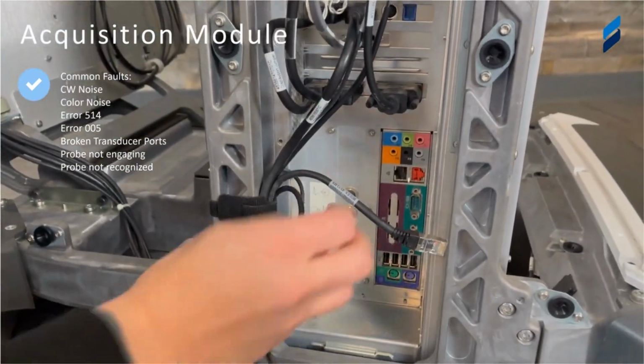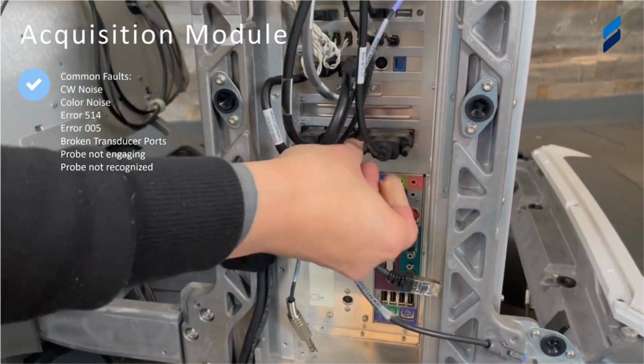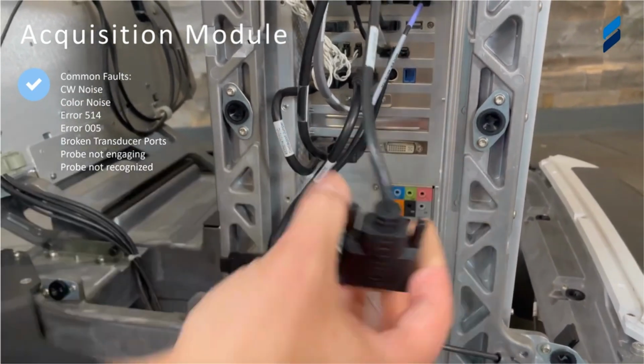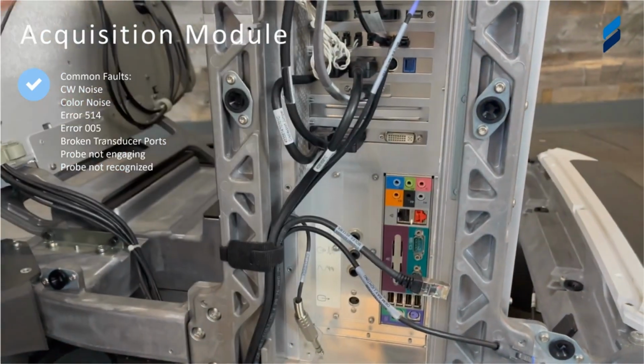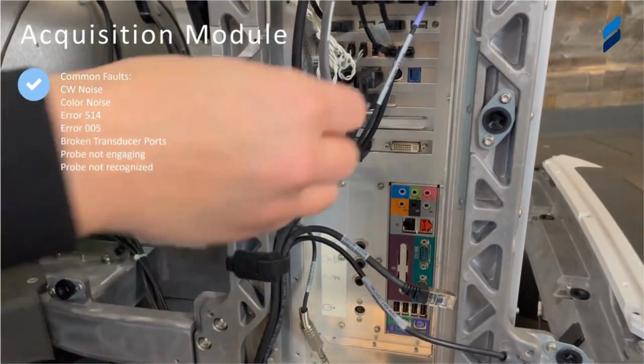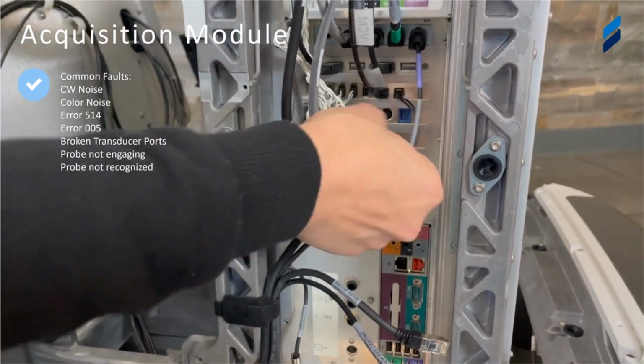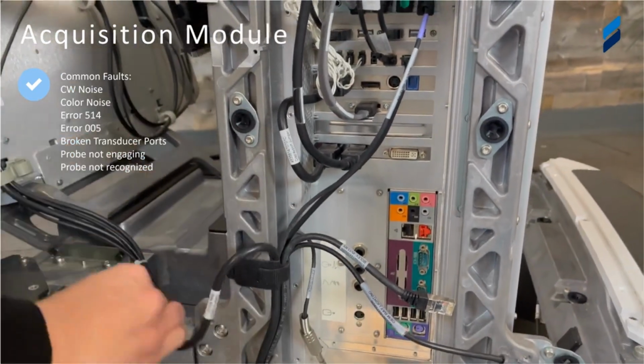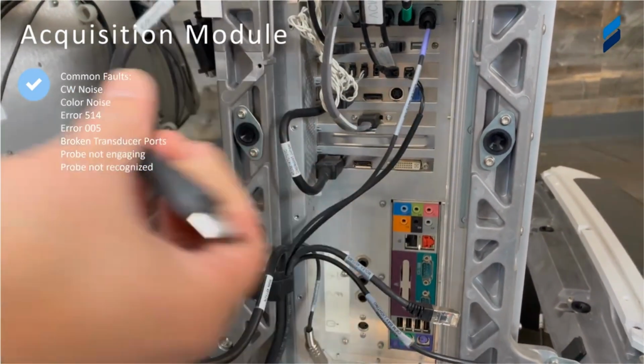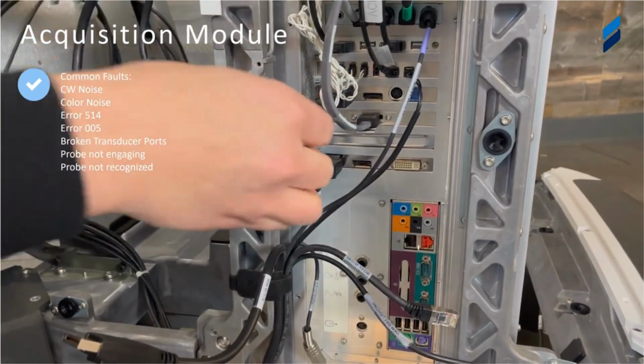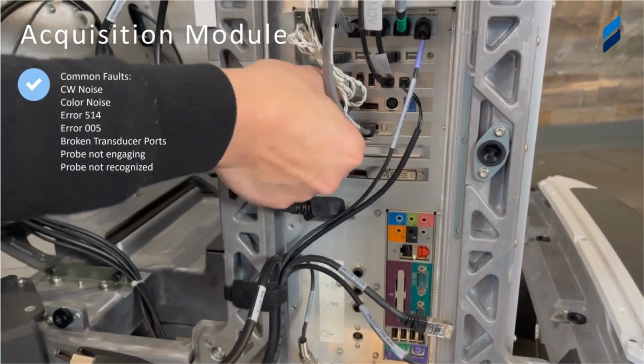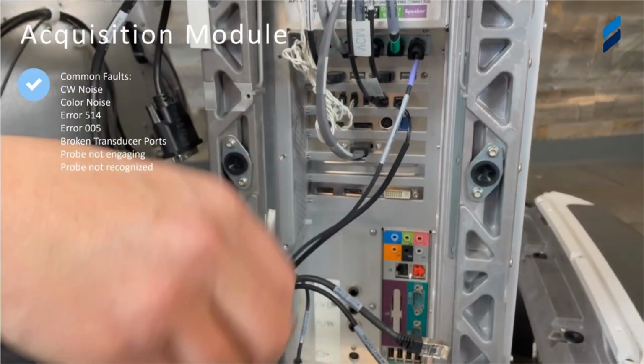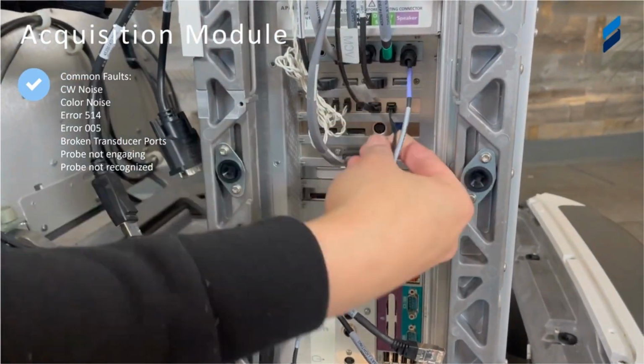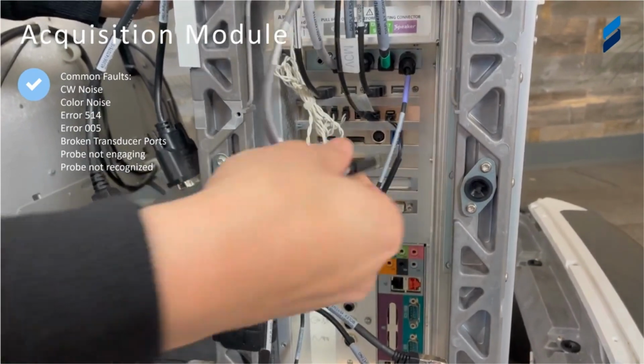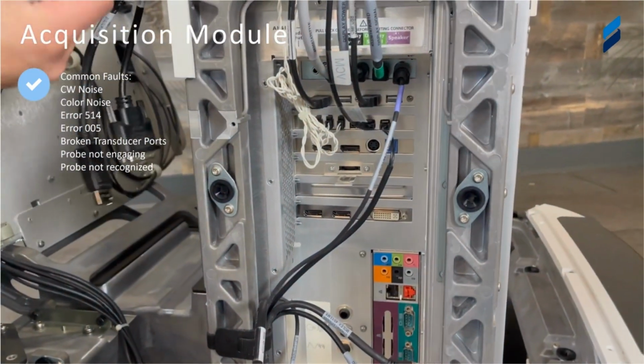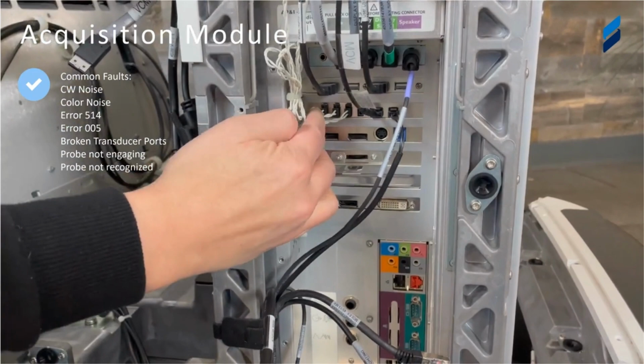Your acquisition module is that front piece that is attached to the e-box, but just for being thorough in this training, we're going to go ahead and remove all the connectors. Take pictures of your connectors and cables and where they go before you start removing them, so you know exactly where they go back. Referencing an external source of where your cables go is absolutely possible. We find that actually ends up taking more time than just pulling out your cell phone and taking a couple of pics on where everything should go. Even better, take a video, strafing up and down, to reference exactly where the cable should go back to when you reassemble the machine.